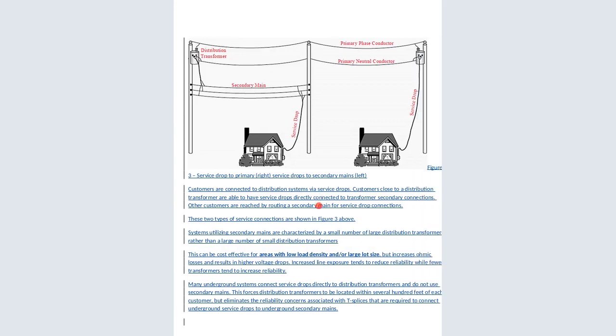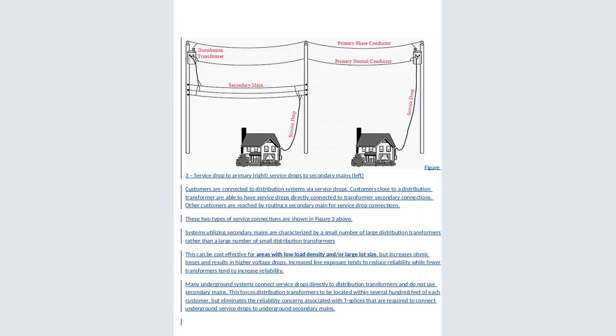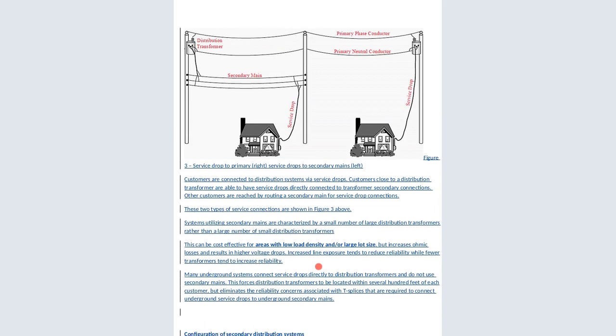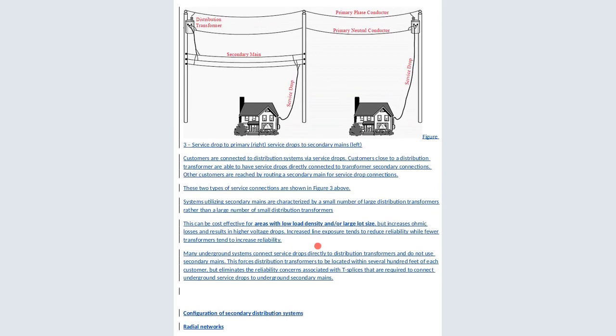You can now see the distribution. Now a distribution transformer is there, the secondary main is there, and then the service drop, the primary phase, the primary neutral conductor. So from the transformer, after it has stepped down, it can take power to the secondary main. Maybe this one needs three phase, that's why it gets this, and this one needs single phase, so it just taps the primary phase and the neutral conductor. So the service drop or primary, right, service drop, secondary main, left.